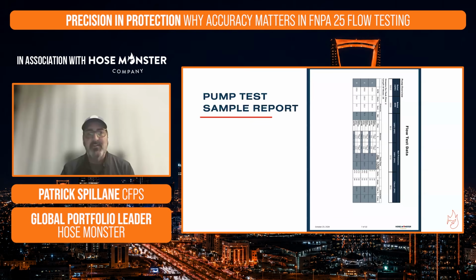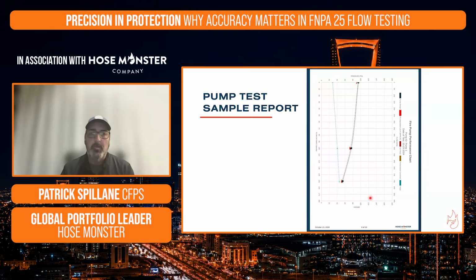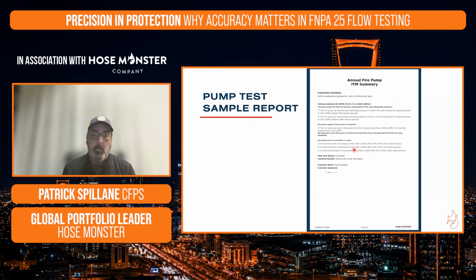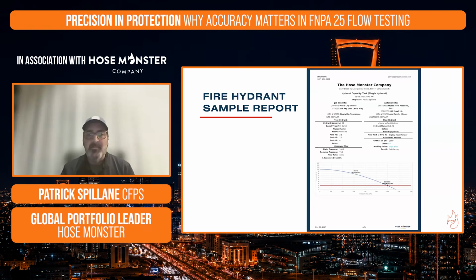And then not only that, but we're going to take all that data and graph it out. This is the more important part, right? We're going to be able to visually see what our observed data was compared to that fire pump's placard, making sure that the fire pump is up to the task and is able to produce enough water to fight a fire, as it was designed to do. Or if it's our fire hydrant test, we're going to create our water flow supply graph so we can see, do we have enough water to design our fire sprinkler system? If that fire sprinkler system is being fed by a municipal water supply, we need to make sure that municipal water supply is up to the task to feed into our fire system. And here, that's where we're going to do that with our hydrant test, to find out how much water is available for that test.